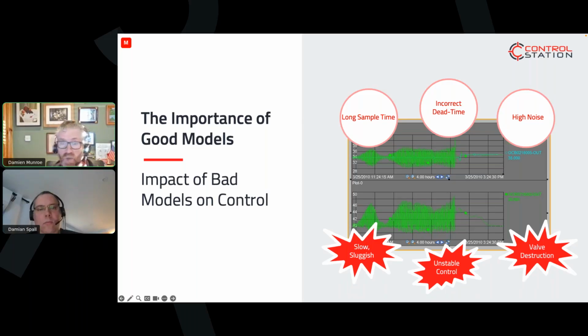You can see the impacts of sample time, dead time, and noise underneath. Slow and sluggish response is because of long sample times. Unstable control if you have incorrect values there. And valve destruction, if there's high noise and high variability, you're going to work that valve longer, further, or harder.